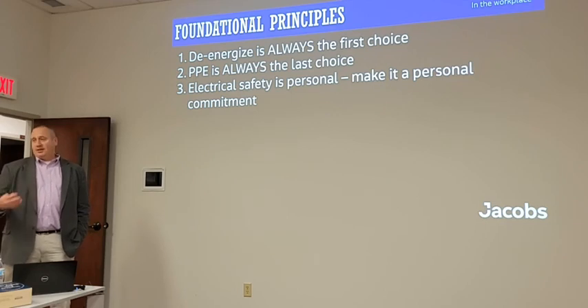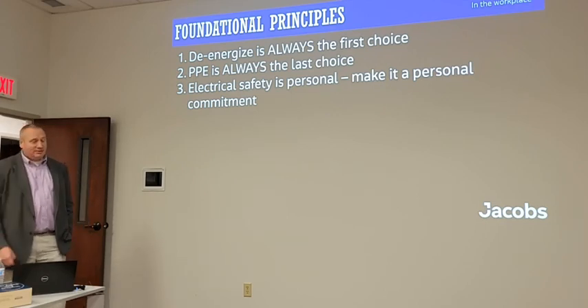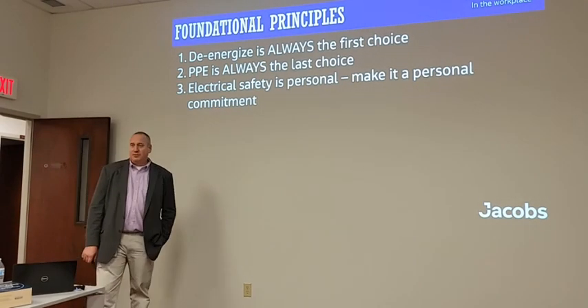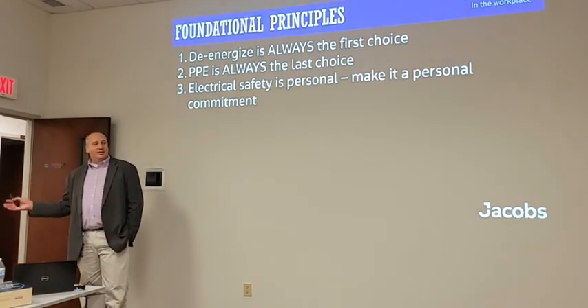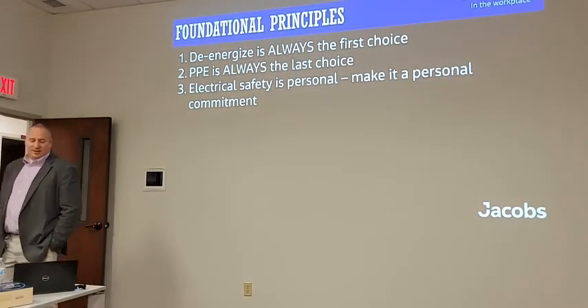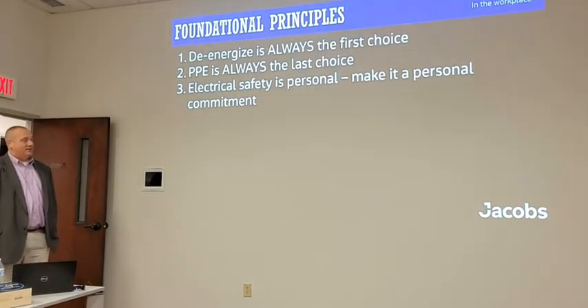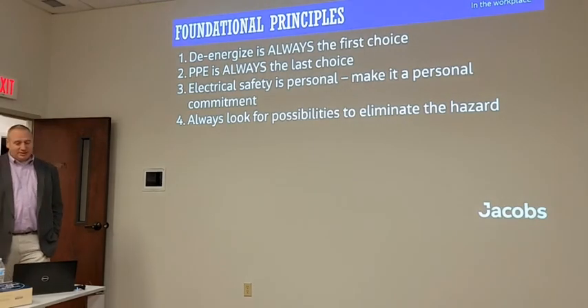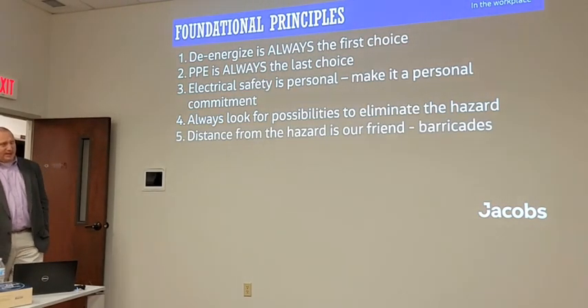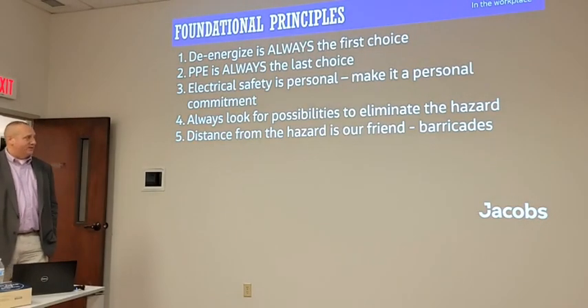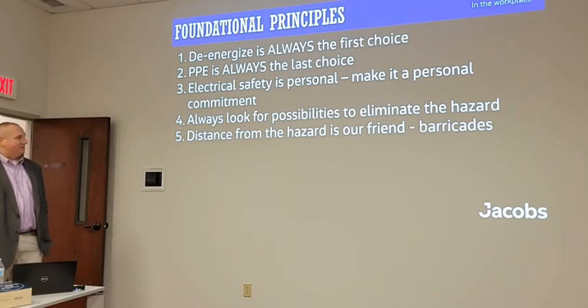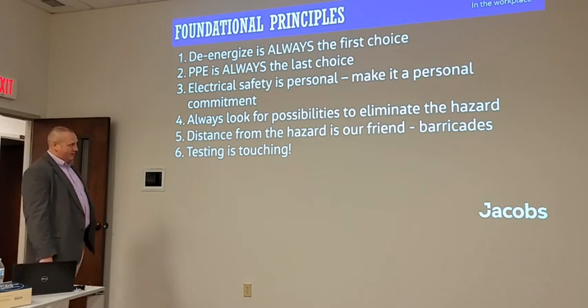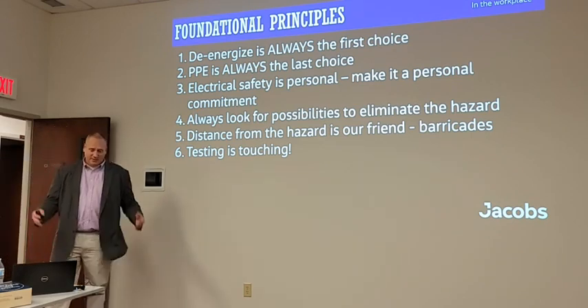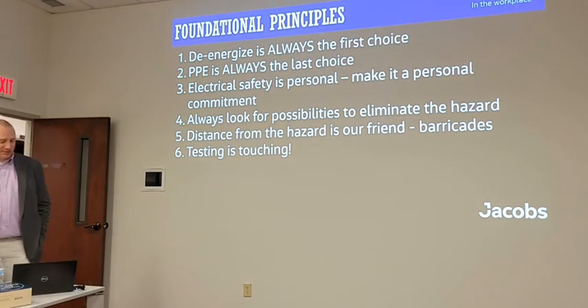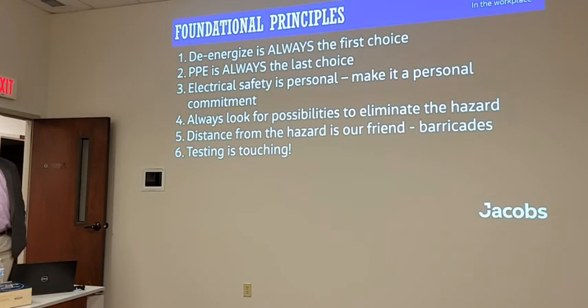I want to know how to not get injured, how do I make sure I go home at the end of the day. Because if it's not personal, if it's just because I don't want to get fired by my supervisor seeing me doing something wrong, the second you know he's not around, then you're going to take the shortcut or do whatever it is that you're not going to get caught doing. So it needs to be personal to really protect yourselves even when nobody's looking. I always look for possibilities to eliminate the hazard. Distance from the hazard is our friend, and so anytime you can use barricades or use remote operations, remote racking, any kind of remote distance is good. Testing is touching. That goes back to the voltage rated gloves. If you're going to be using a digital multimeter over 50 volts, you should be wearing your voltage rated gloves because those test leads aren't insulated for your protection.